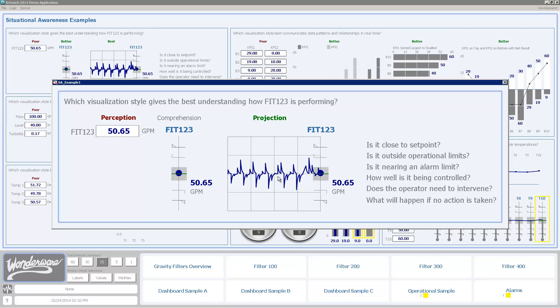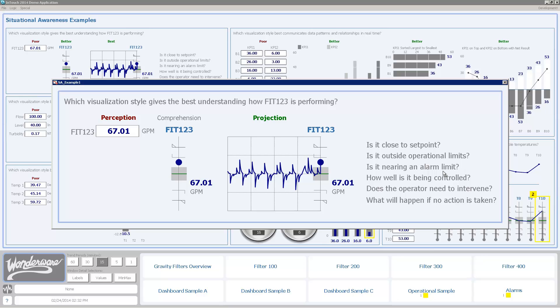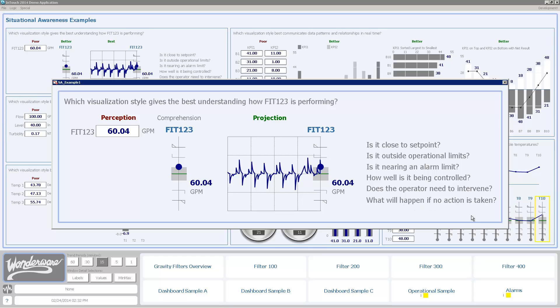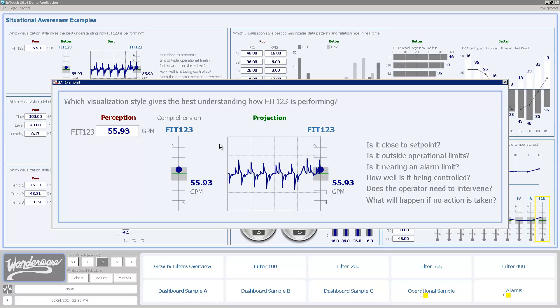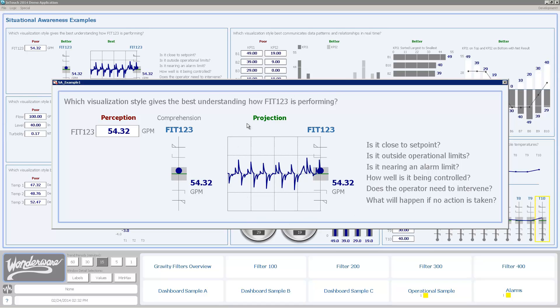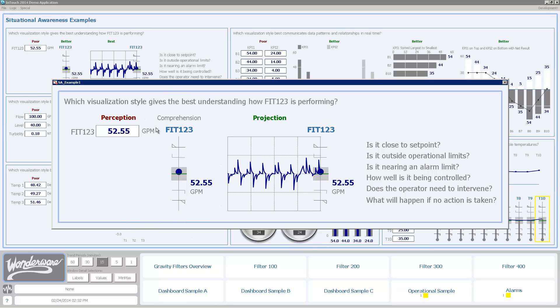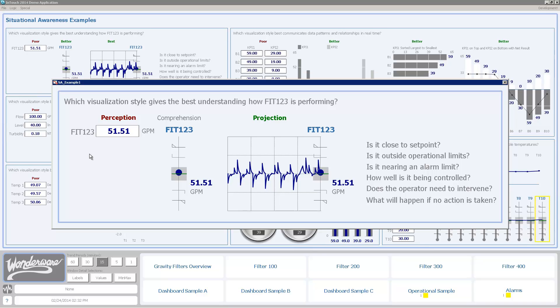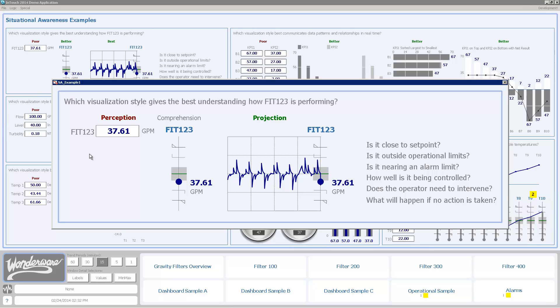So when I look at these questions here on the end: Is it close to set point? Is it outside operational limits? Is it nearing an alarm limit? How well is it being controlled? Does the operator need to intervene? And what will happen if no action is taken? I'm able to answer these questions much better with this symbol here on the right which is utilizing projection. I can sort of get many of these answers with comprehension. Really, I can't get very much out of this first one which is perception. And unfortunately, this perception technique is the one that most people utilize today, and why we saw a need to introduce methods and design elements to make this easier.